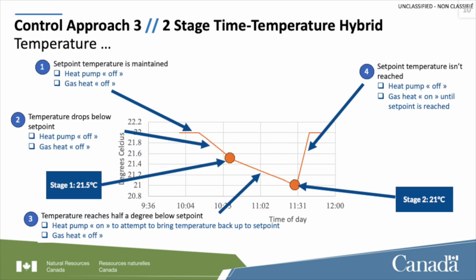Another possibility is the control approach, a time-temperature hybrid. Nothing's on, the temperature comes down, and the heat pump comes on in an attempt to bring it back up, but it can't. This happens in colder temperatures where the unit just doesn't have the capacity to reach the comfort temperature we require. So we let it go for a bit and give it a chance. The building code says we have to give it that chance. But at a certain point, you know what, you gave it a good shot. I'm afraid the 100,000 BTU furnace is going to have to kick in down in the basement and carry this the rest of the way.